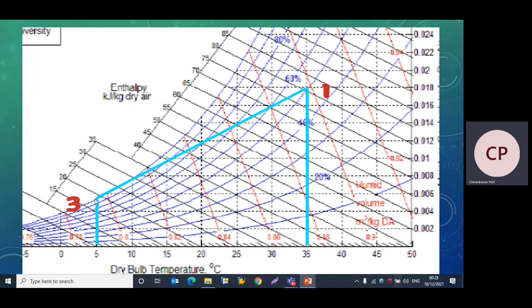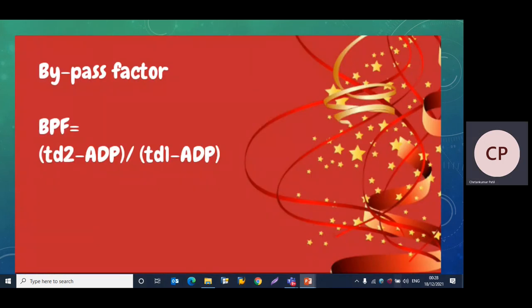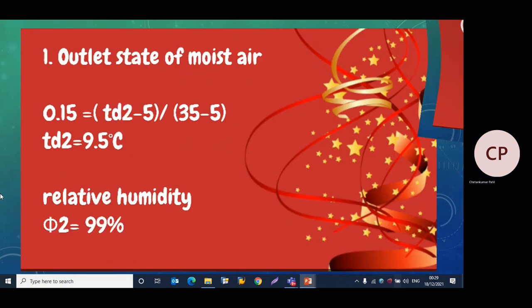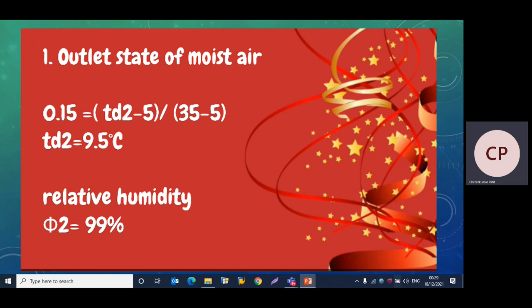Point 1 and point 3 are now selected, and we join these two points. To plot point 2, we first find the dry bulb temperature at point 2 using the bypass factor formula: Bypass Factor = (Td2 − ADP) / (Td1 − ADP). Substituting: 0.15 = (Td2 − 5) / (35 − 5). Solving for Td2 gives 9.5°C.